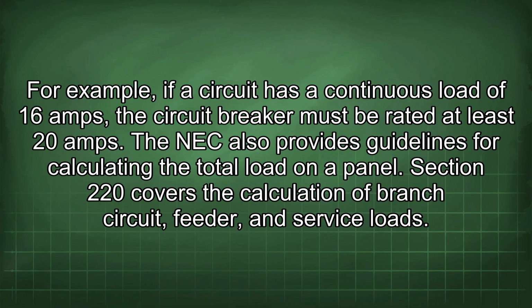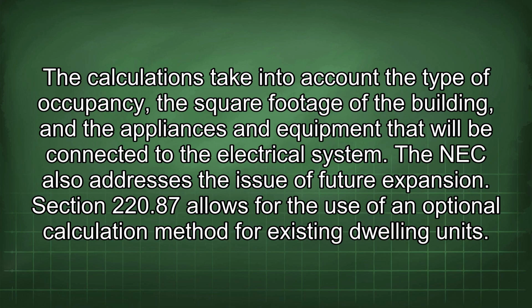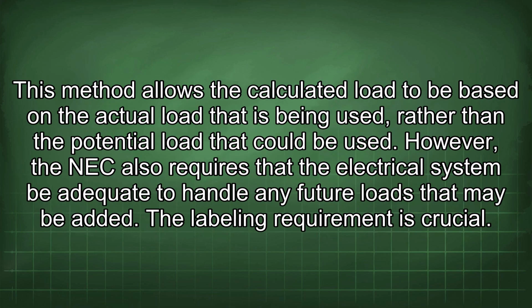The NEC also provides guidelines for calculating the total load on a panel. Section 220 covers the calculation of branch circuit, feeder, and service loads. The calculations take into account the type of occupancy, the square footage of the building, and the appliances and equipment that will be connected to the electrical system. The NEC also addresses the issue of future expansion. Section 220.87 allows for the use of an optional calculation method for existing dwelling units. This method allows the calculated load to be based on the actual load that is being used, rather than the potential load that could be used. However, the NEC also requires that the electrical system be adequate to handle any future loads that may be added.